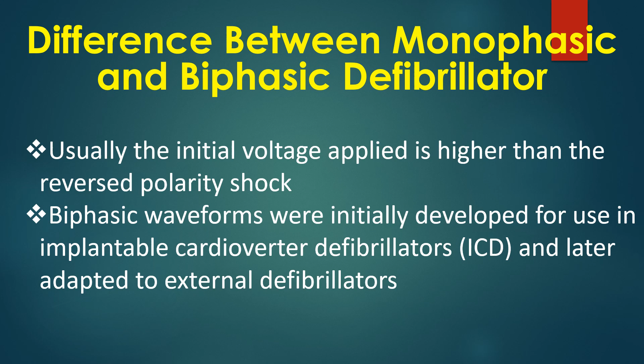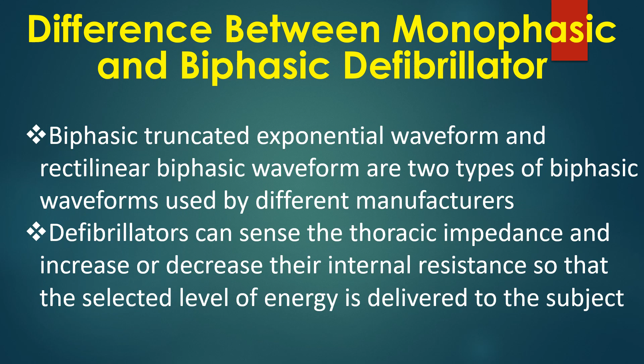Defibrillators can sense the thoracic impedance and increase or decrease their internal resistance so that the selected level of energy is delivered to the subject. Biphasic shocks are more effective than monophasic shocks and need lesser energy. Typically, when 360 joules are delivered for defibrillation in a monophasic defibrillator, 200 joules are given in a biphasic defibrillator.